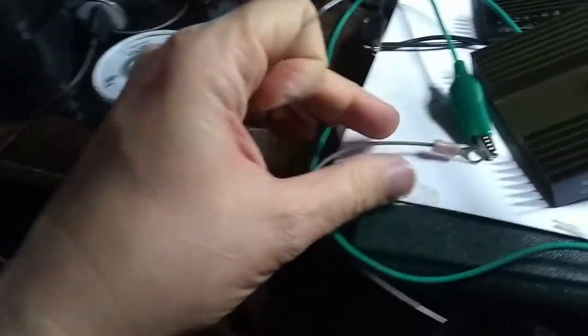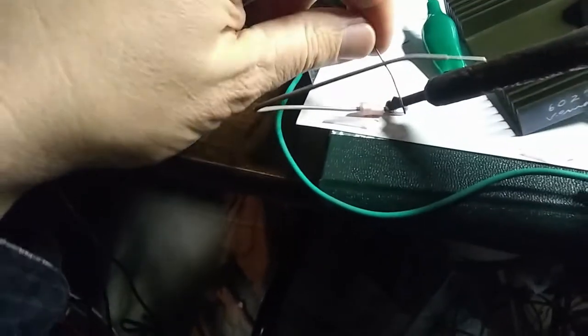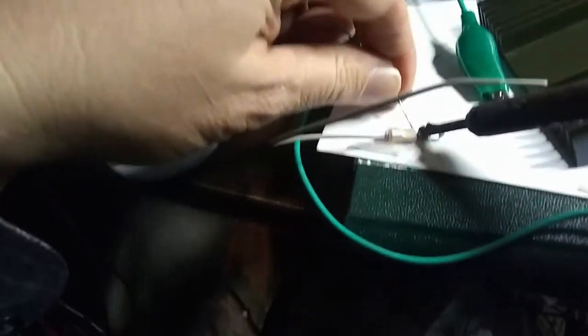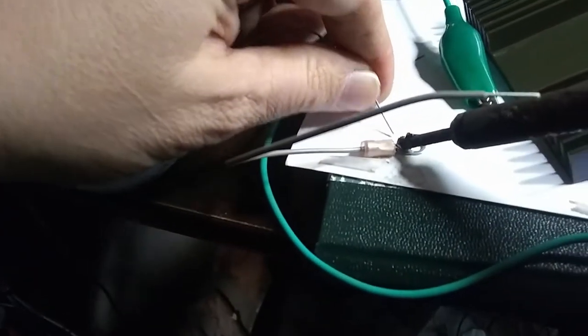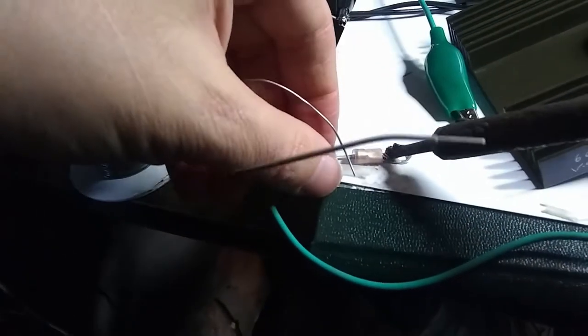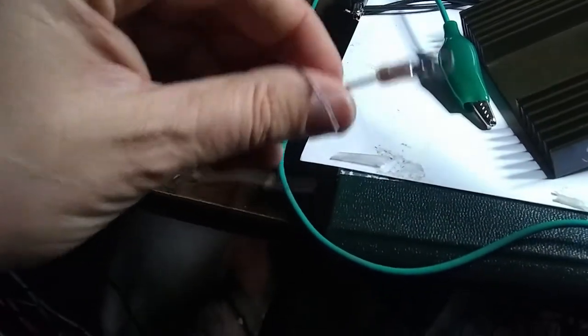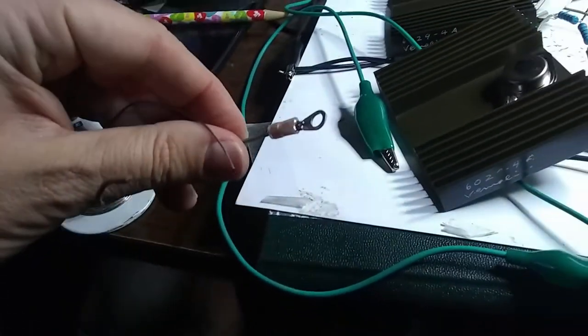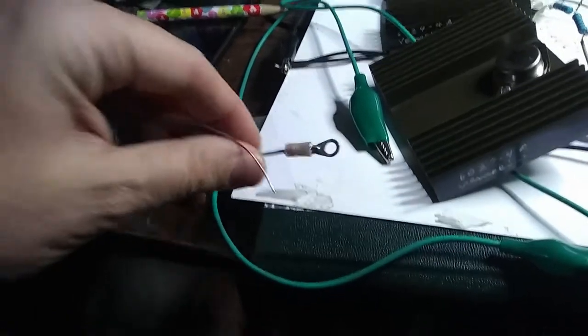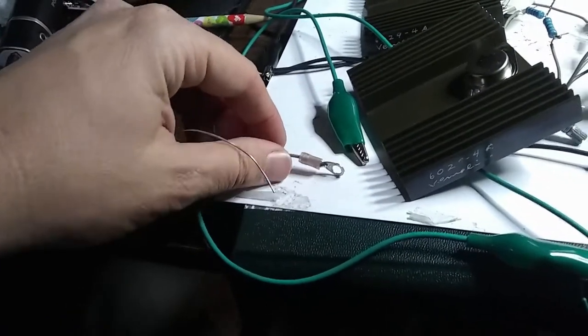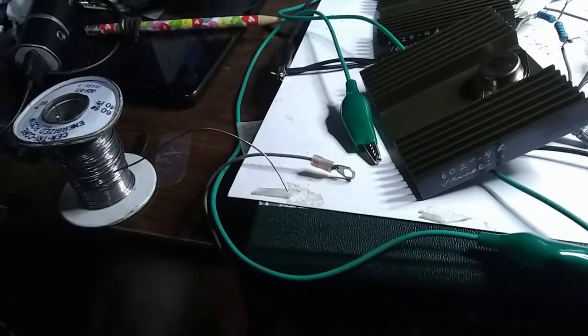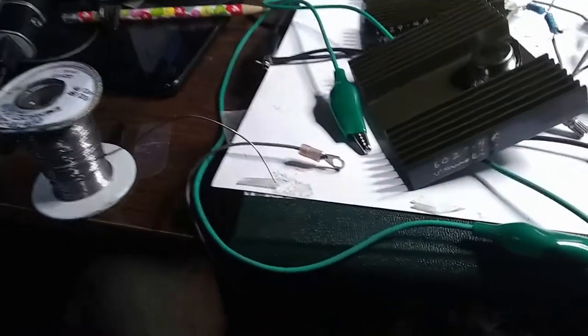Did I mention sometimes it helps when you're crimping lugs to also solder them, because if you don't get the crimp good they can come out. A crimp and a solder makes it a lot harder for it to come out, makes better conduction. There we go, okay soldered and crimped. So this lead actually just came off, I pulled it out when I was going to try to solder this thing up. So that's a good tip: solder your lugs as well as crimp them.